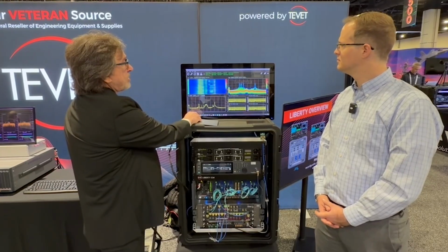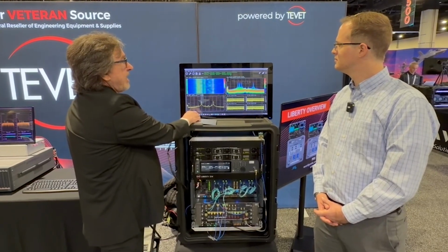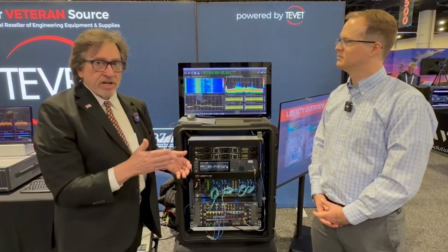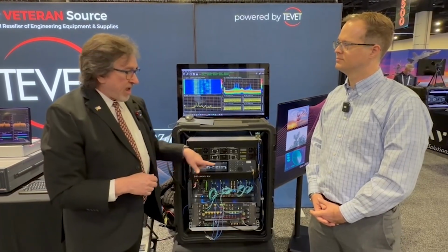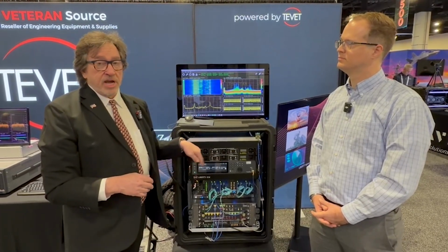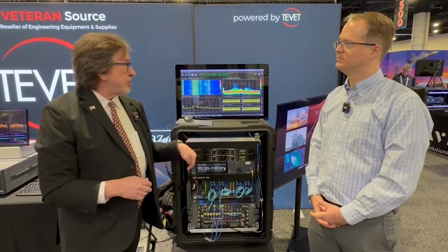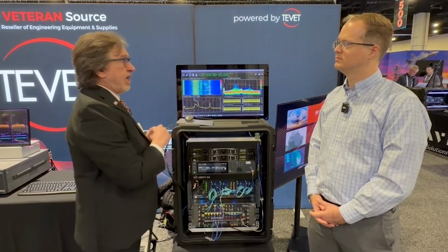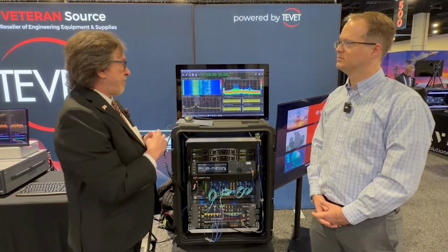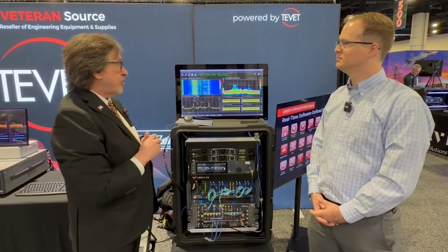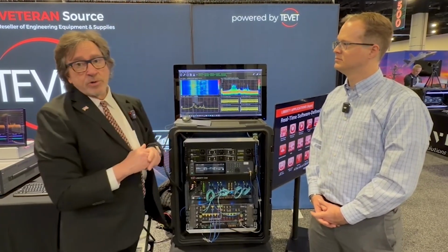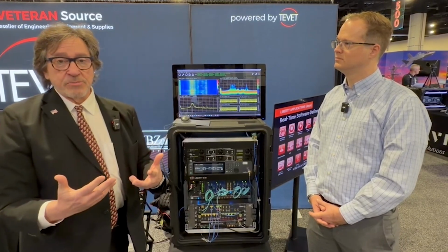I can come over to the histogram and select which of the channels I want to visualize. The important point here is that all 4 are running at the same time. All 4 can be configured, and we can then choose which you want to look at. In the lower right-hand corner is recorded data. I showed that earlier. We'll talk about that when we get into how to set this system up.